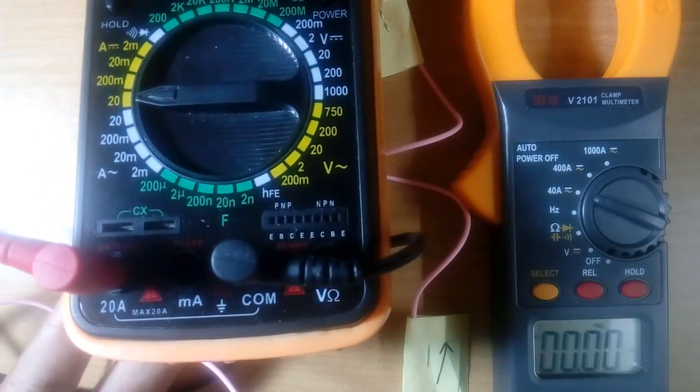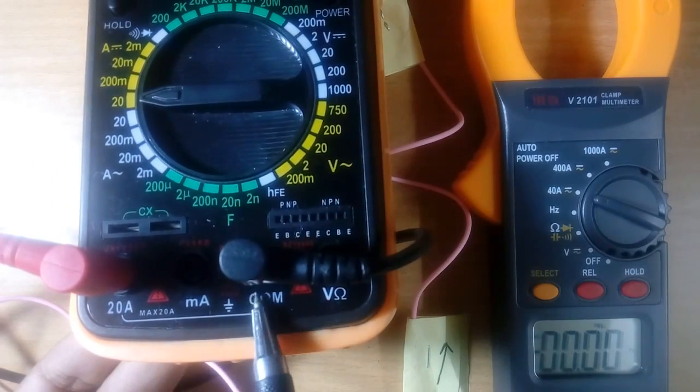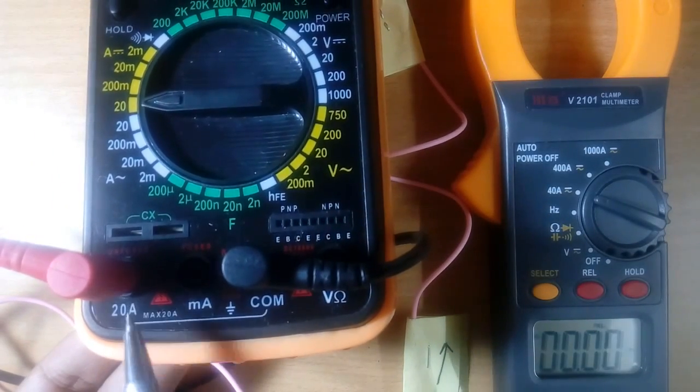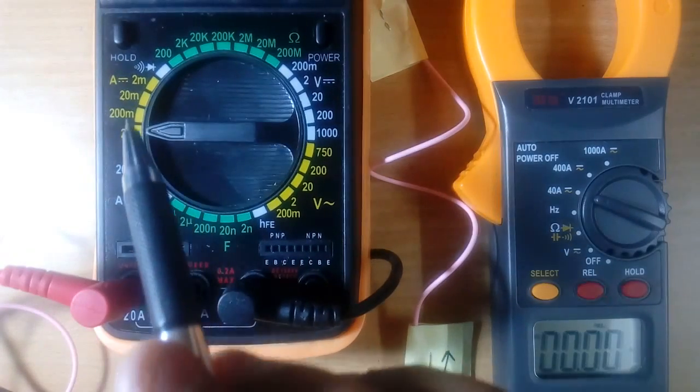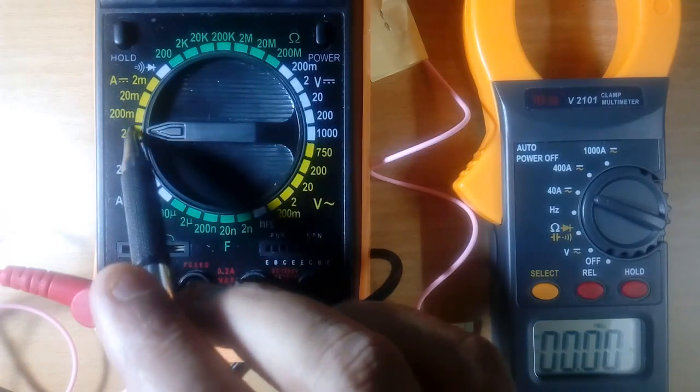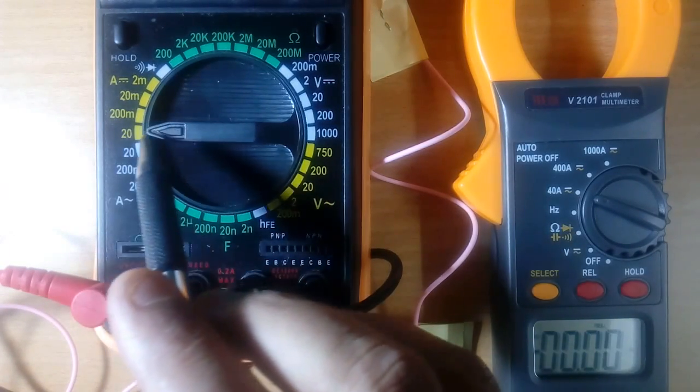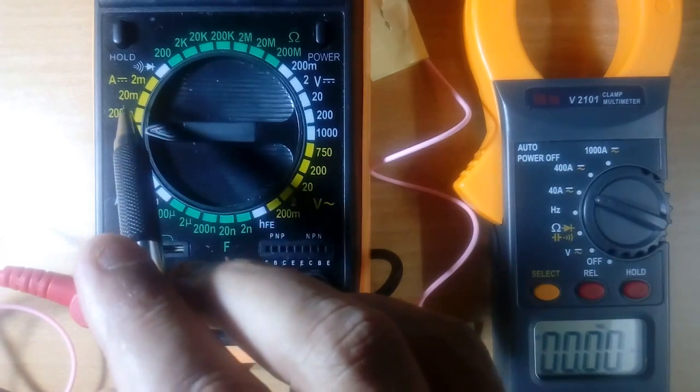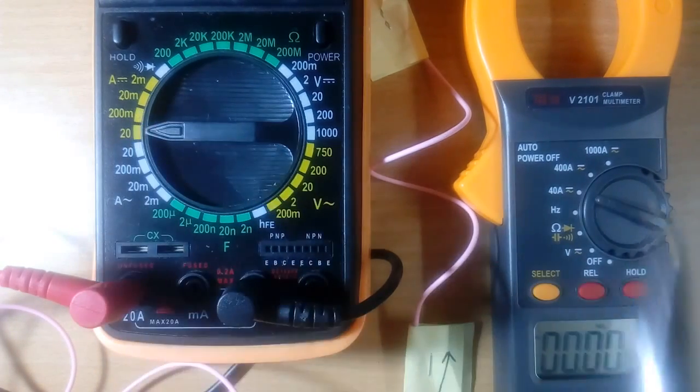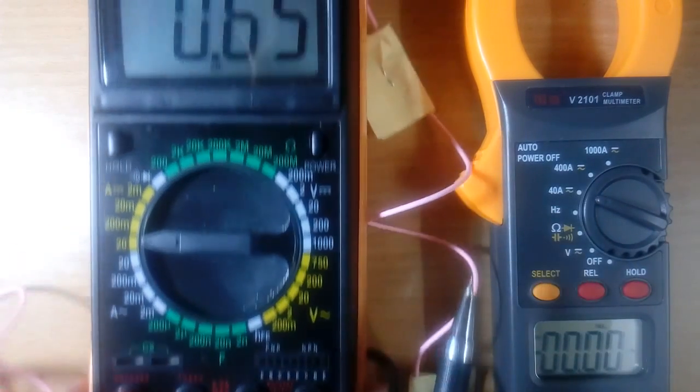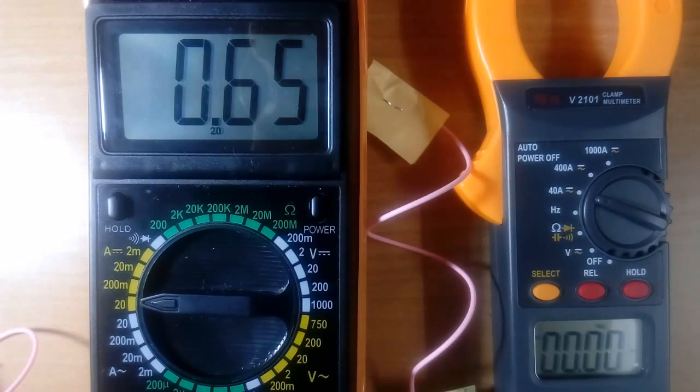In incommer, one wire has connected to com, another 20 Ampere. Because I know my current is more than 200 mA, so I have put my scaling at 20 Ampere. If I put my scaling at 200 mA, digital multimeter may go bad. It is very simple.